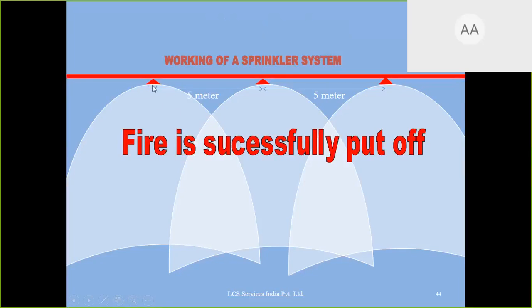Whenever the sprinkler runs, it will sound an alarm in the fire pump house. Somebody has to go where the sprinkler is working. He has to ensure the fire is controlled and he has to manually switch off the pump. Right? Until you switch off the pump, it will keep running.